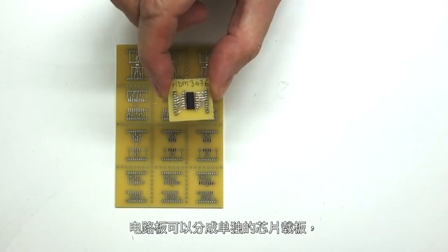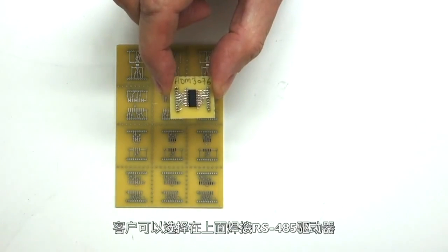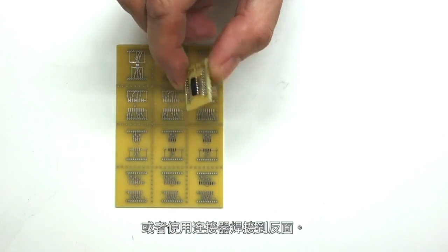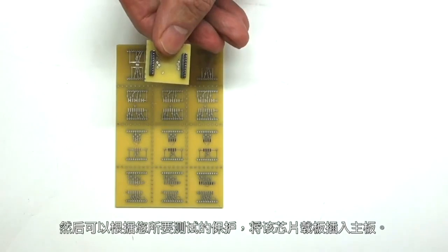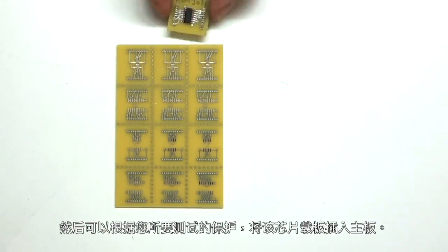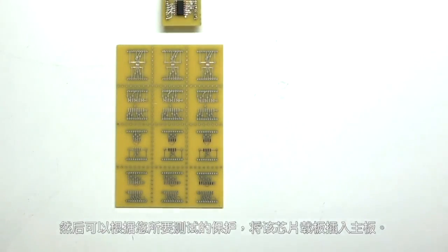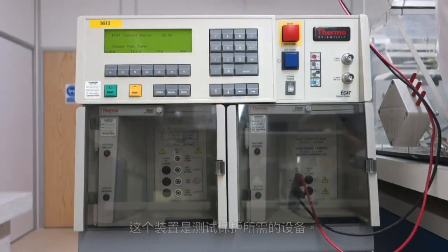The board can be separated into an individual chip carrier, the customer's chosen RS-485 driver soldered onto it, and connectors soldered onto the reverse side. This chip carrier can then be plugged into the main board according to the protection that you intend to test against. This unit is the equipment needed to test such a board.